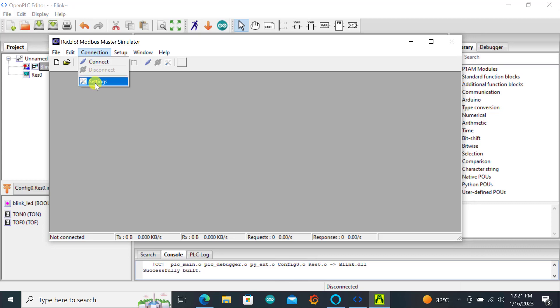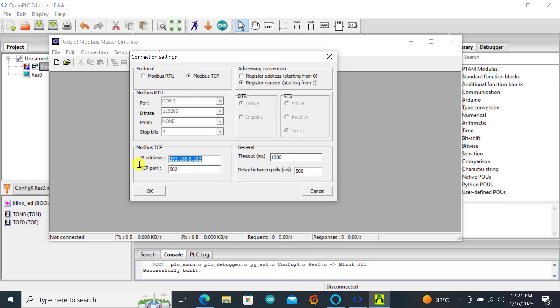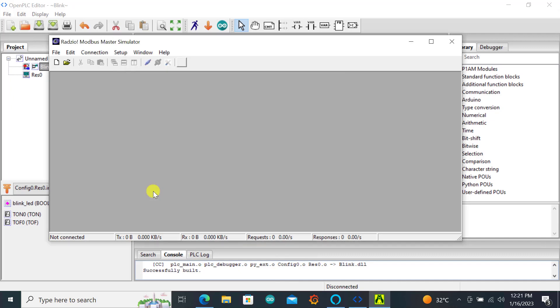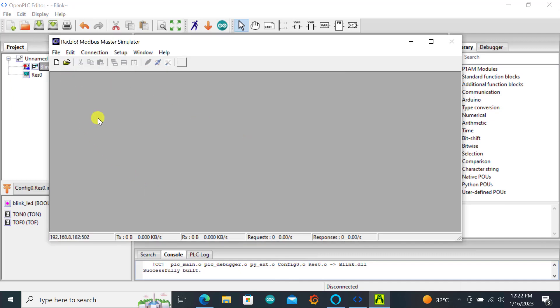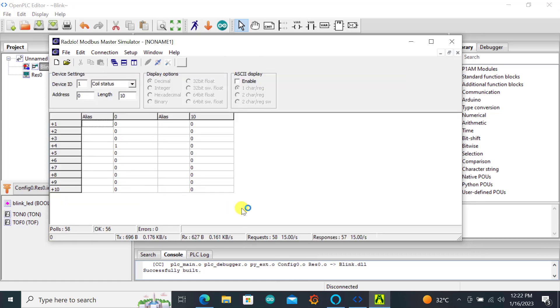We have the Modbus tester installed and open. Now we need to configure it. You go to connection and then you go to settings. Here you have the possibility to choose between Modbus RTU or Modbus TCP. In our case we've used Modbus TCP so you select Modbus TCP. You come to the IP side and specify the IP of the ESP which is already specified. TCP port remains the same. You click OK and then you can click on the connection again and click on connect.